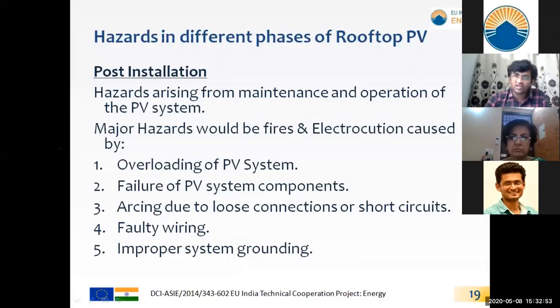In the long run, overloading might develop heat, and there may not be proper ventilation. At the time of installation it may seem correct, but once running you might find the ventilation is not sufficient, be it for your battery system or your PV system. So you have to make sure the ventilation is good.